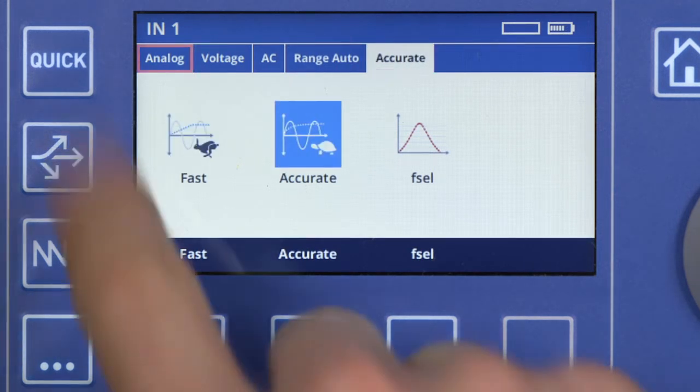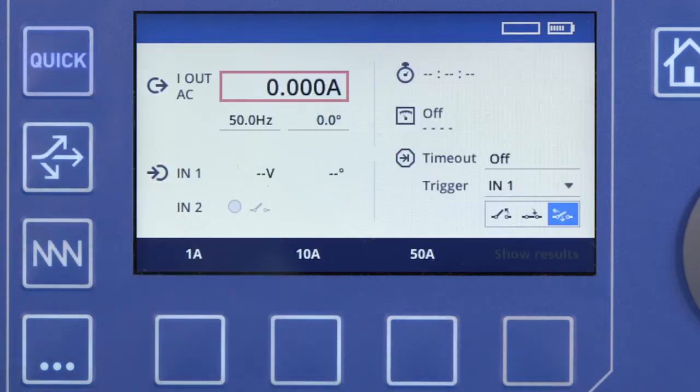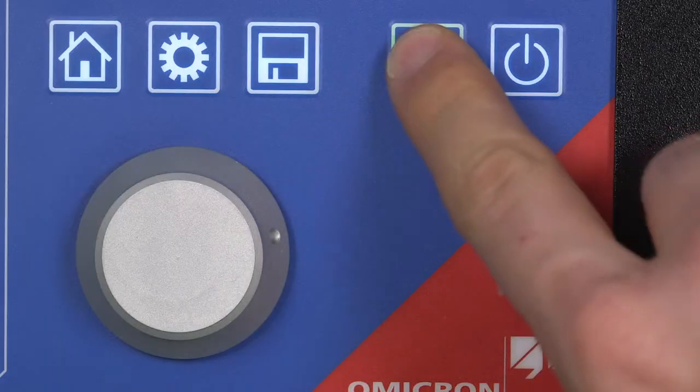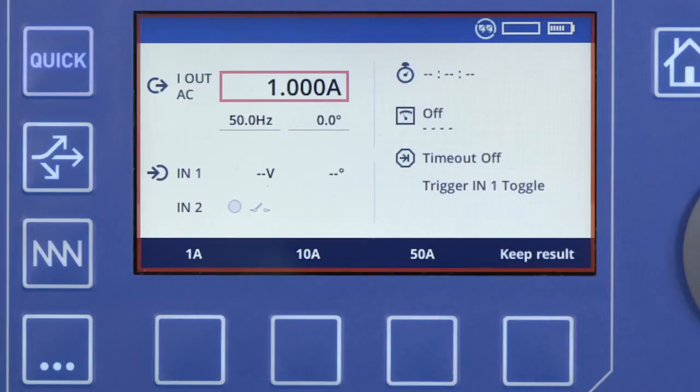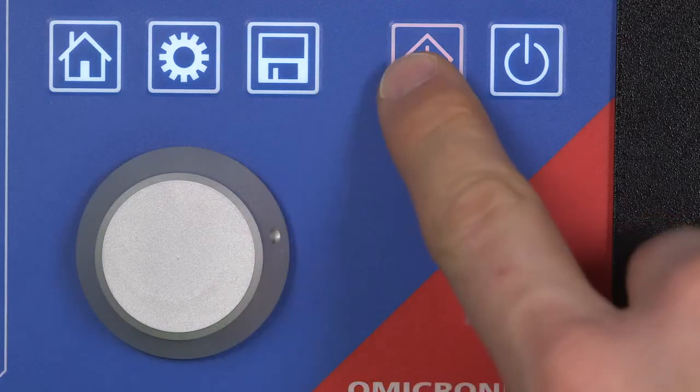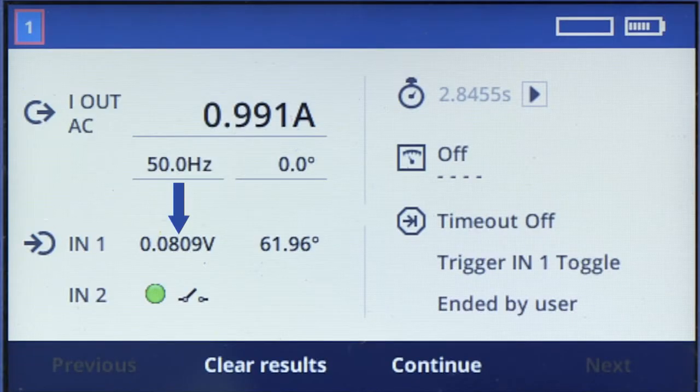Please verify that the CT's secondary loop is closed by injecting 1A for a few seconds. Now you should be able to see a few millivolts at IN1. If the value is above 1 volt, please stop the test and check the wiring as the CT's secondary side might be open.